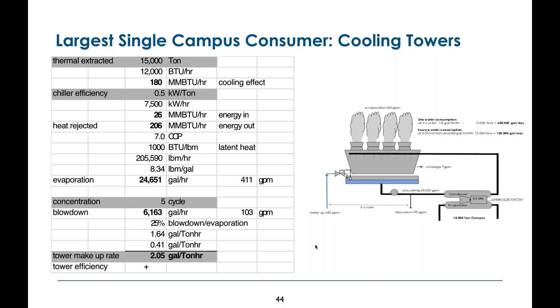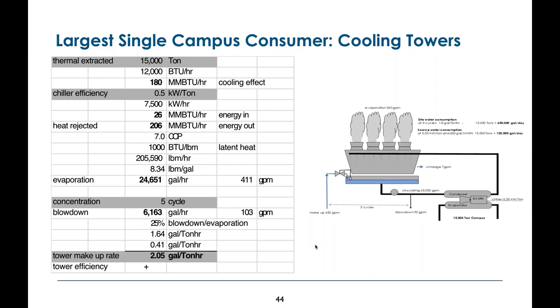At the bottom of this, at five cycles, that represents 25% of the water you're evaporating being wasted in order to hold five cycles. Pretty typical in the Southwest to run at five cycles, maybe a little lower, which gives us a total makeup rate of 2 gallons per ton-hour - an interesting number when you think about gallons of milk and ton-hours of air conditioning.